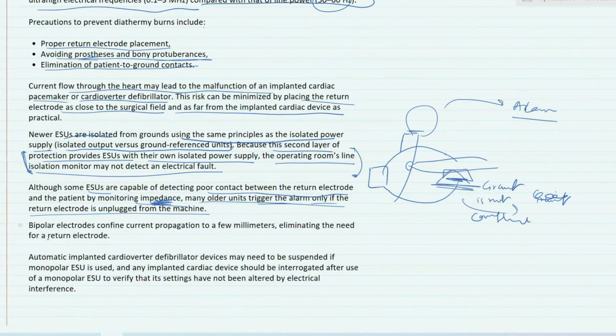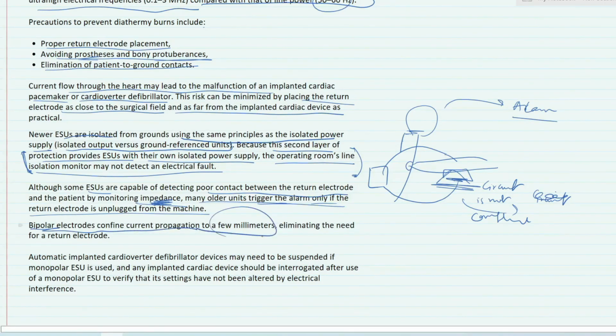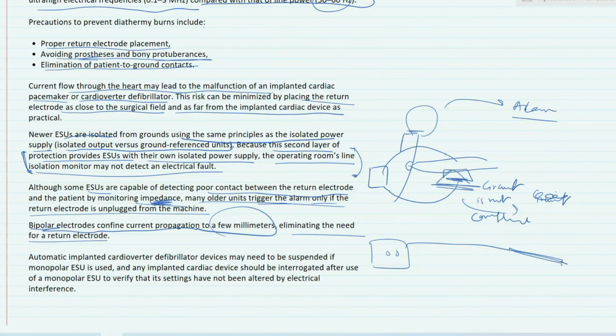Now there's another thing we can use, which is bipolar electrodes, which confine current propagation to a few millimeters, eliminating the need for a return electrode. Another way is that we have this ESU and this electrode, and instead of the plate we have the returning wire, which is wound into the probe and goes back to the ESU, to the source, and this completes the circuit here. This is called bipolar diathermy, right?